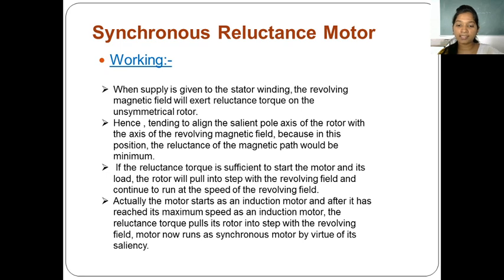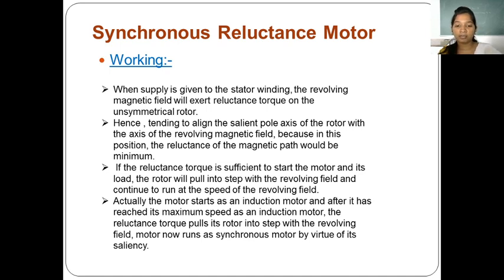After the motor has reached its maximum speed as an induction motor, the reluctance torque pulls its rotor into step with the revolving field. The motor then runs synchronously by virtue of its saliency. This is the synchronization between the stator and rotor field — if the rotating magnetic field is at synchronous speed, the rotor also starts rotating at that same speed. Hence we call it the synchronous reluctance motor.